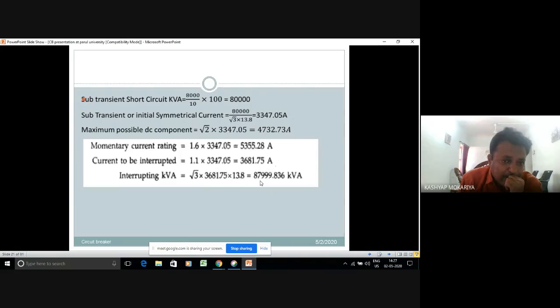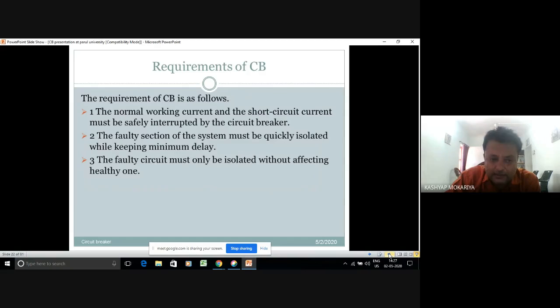The third thing is that some people think of MATLAB. Suppose I want to visualize, for this amount of high voltage line and this rating of breaker, how my waveform will look for this fault current, the three phase dead short circuit currents, and what will be its effect after a particular simulation runtime of milliseconds or seconds. So in MATLAB also people can plot the responses by taking a nominal T method or nominal pi method. You can have a generator, a transformer, a load as an induction motor, a breaker, and a fault block, and you can just visualize the rating. But surely you have to calculate and deduce this type of ratings when you are in the industry, what the ratings of the breaker which has to be fitted will be.